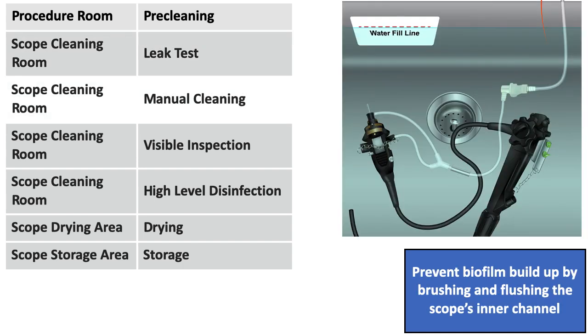Following that, you do the manual cleaning, which involves brushing and flushing of the scope inner channels. And when it comes to brushing, picking up the right sized brush is really critical. Every small detail in the manual cleaning process makes a big deal. You should do the manual cleaning under full immersion so that the scope gets cleaned properly.